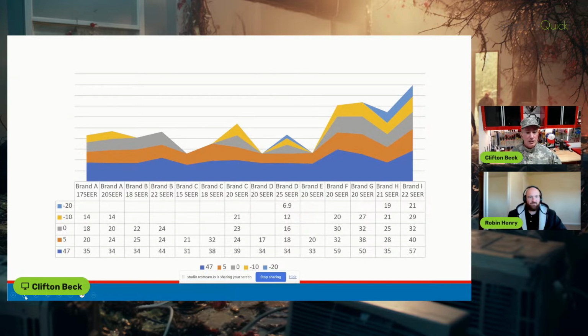I did a whole show on heat pump performance, looking at different models, because you may require a heat pump with better capability at lower temperatures, or you may not, depending on the ambient conditions in your zones. We looked at different brands, all 3-ton heat pumps matched to an air handler. It's critical to do an actual heat load calculation on the structure, reduce the heat load as much as possible, and then select the correct equipment for your area, because they're not all the same.